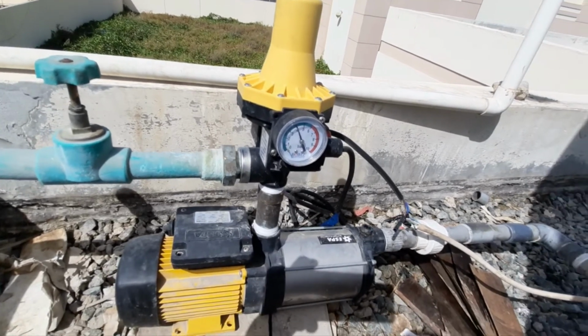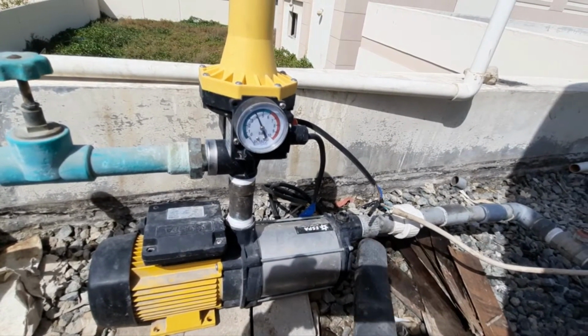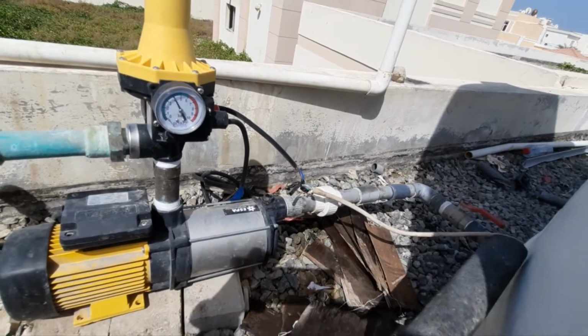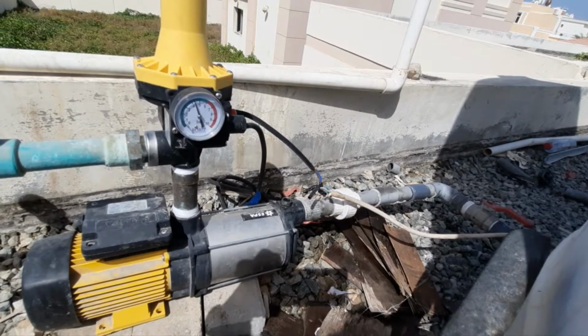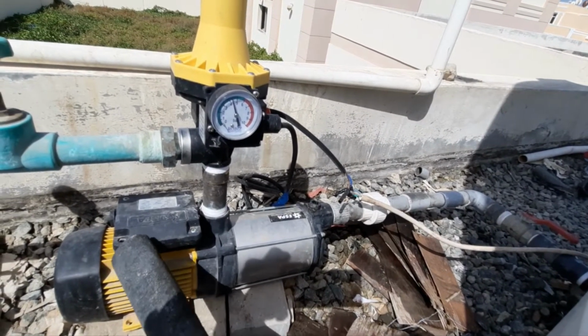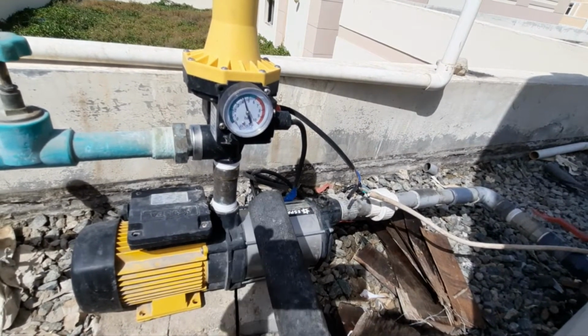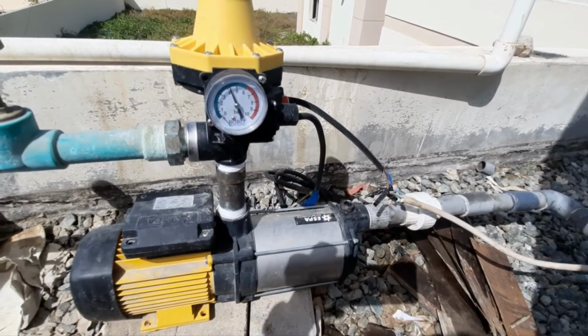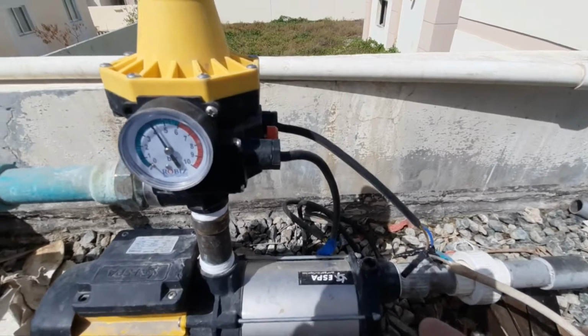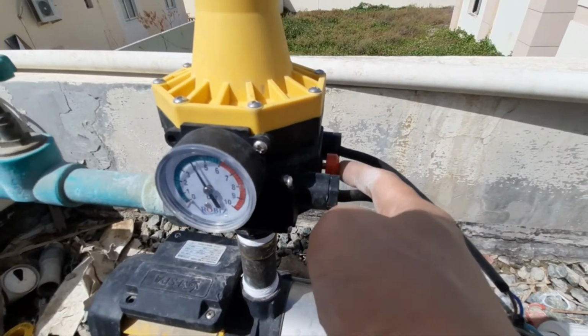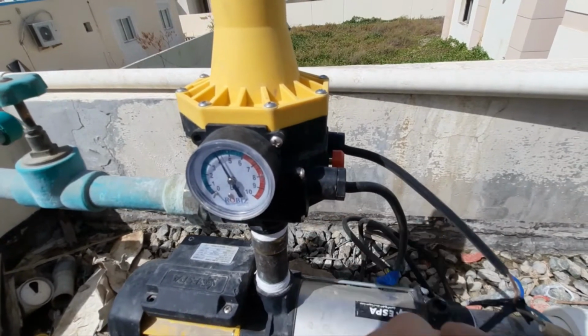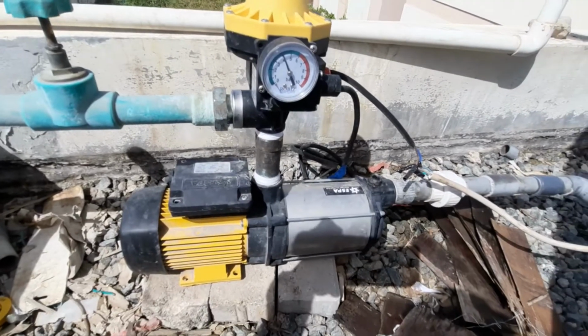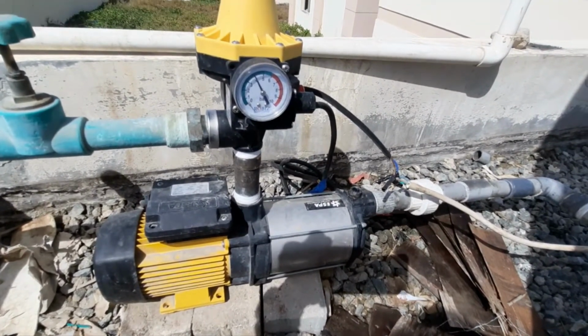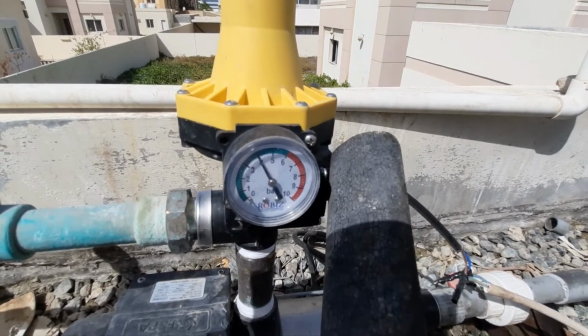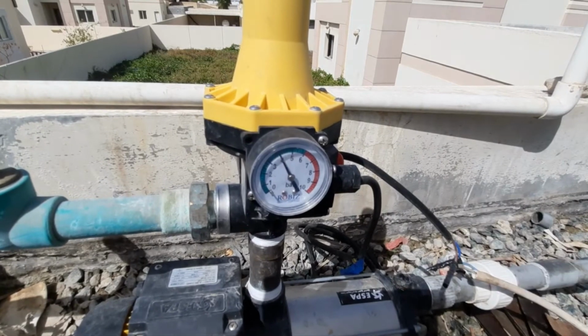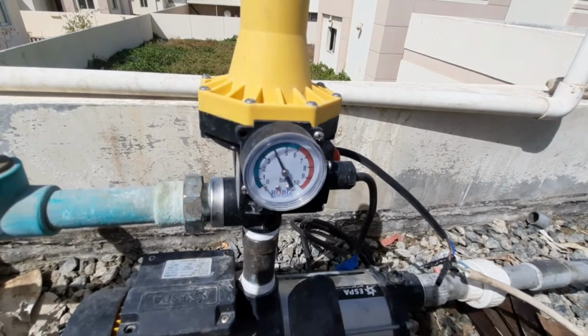And if, for instance, the supply of water from the tank cuts off and the motor or the pump trips off or turns off, you can reset the switch, or the pressure switch, by pressing this red push button here. Just press this for a few seconds and then the pump will restart again. So now what we are going to do is open this pressure switch, in order for us to learn what is inside the pressure switch mechanism and how the system works.